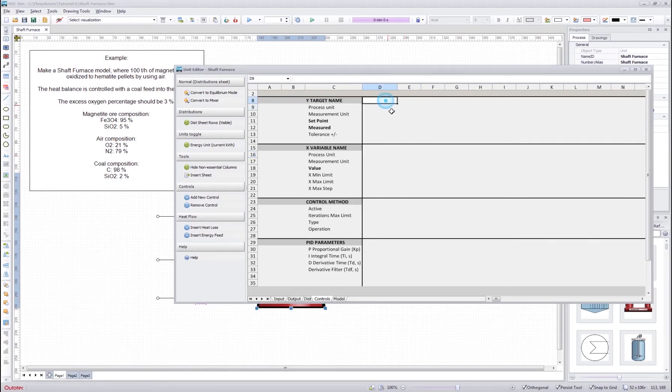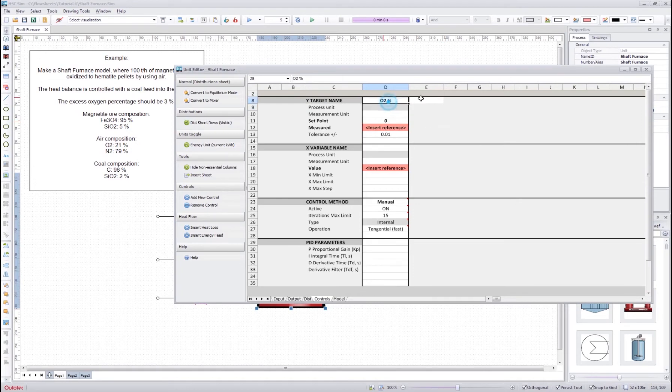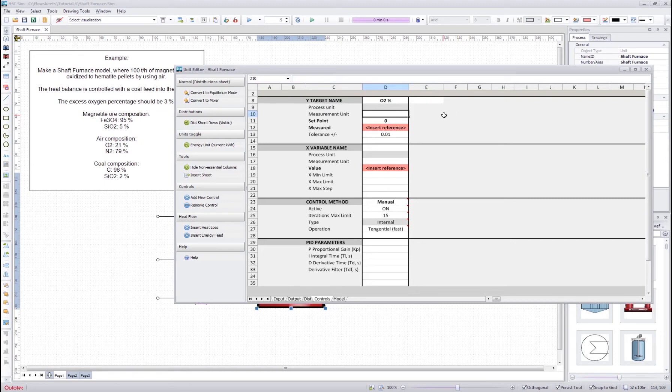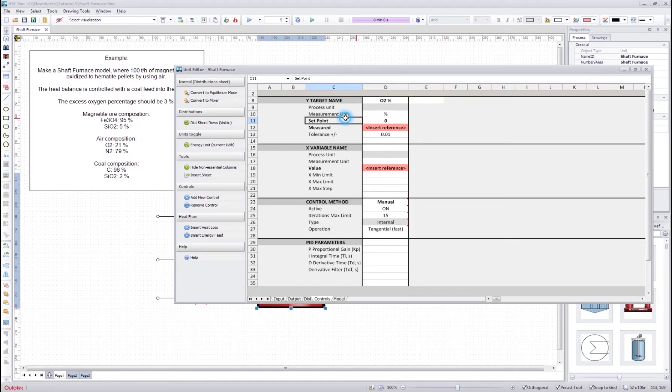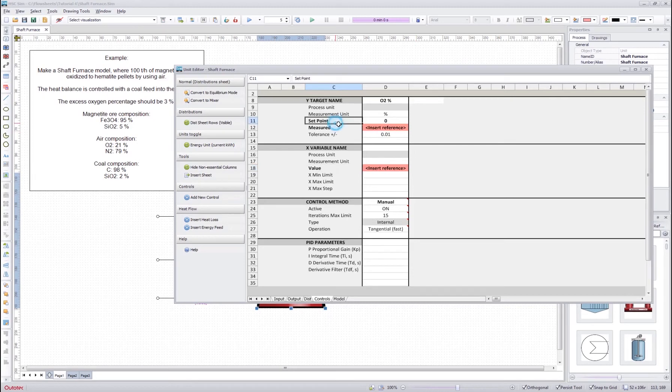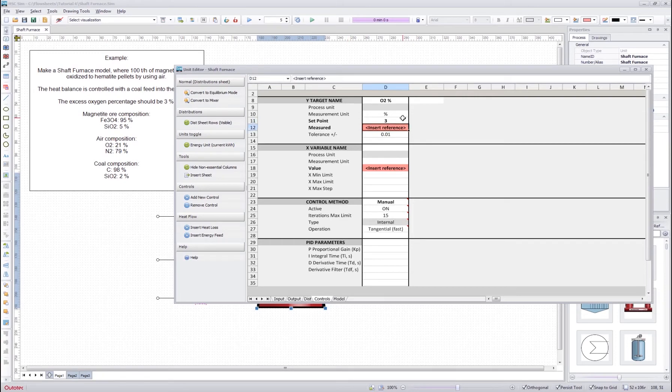We start by making the oxygen percentage control. So we write title here oxygen to percentage and when we write into this white cell it will open up the rest of the cells for editing. This process unit will come automatically. We select percentage and then we have the set point. The set point, measured, and value cells are the most important cells of the control definition. In the set point we put the value that we want to reach. In this case we want the excess oxygen percentage to be 3, so we will insert 3 over there.